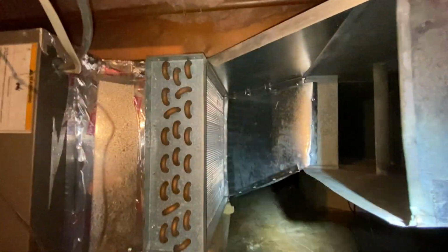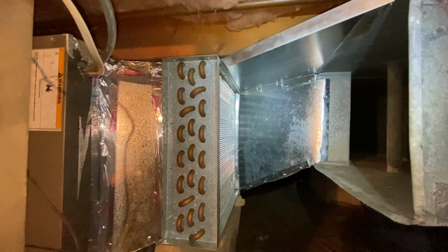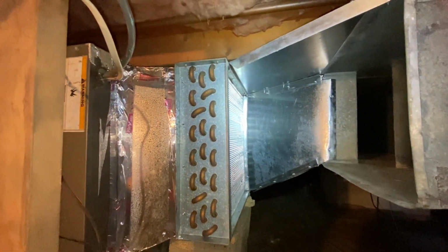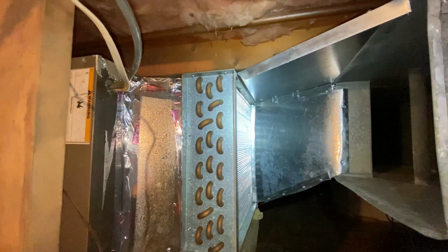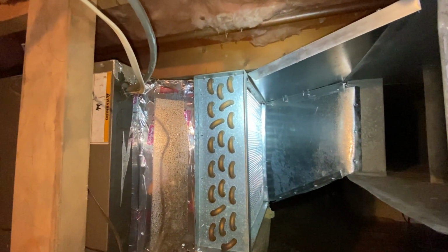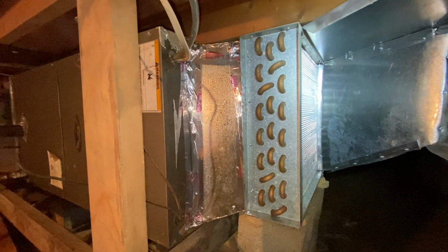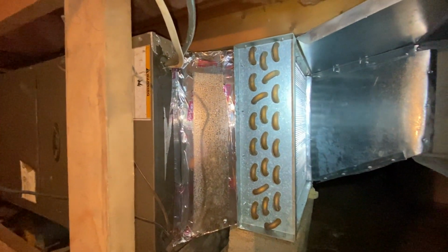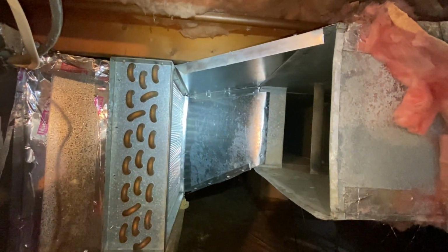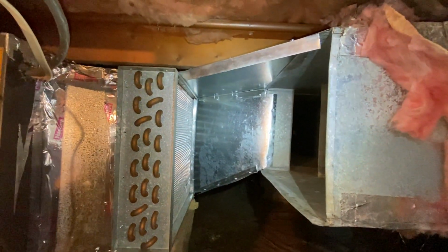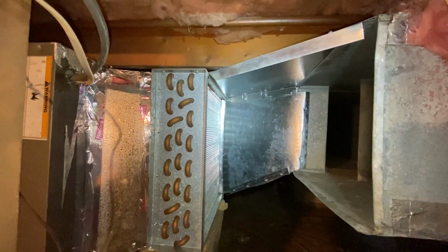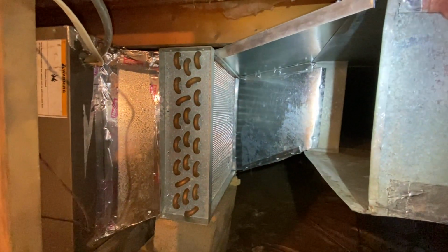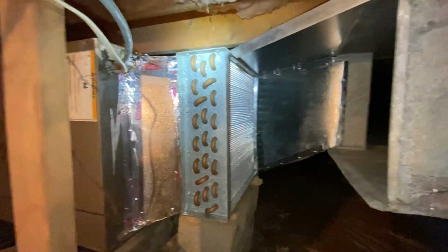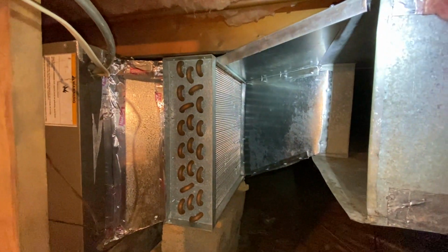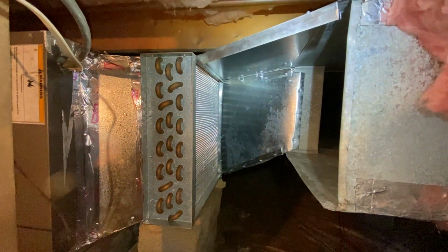I'm glad I did what I did, because it's coming together nicely. So we've got an 18 by 21 heat exchanger, a 20 by 21 opening to the end of the air handler, and then we've got a 12 by 20 that's offset, but it expands and then contracts again after it goes through the heat exchanger, which is exactly what I want. The airflow will slow down just a little bit, get some good thermal exchange, and then speed up again as it goes through the ductwork into the house.